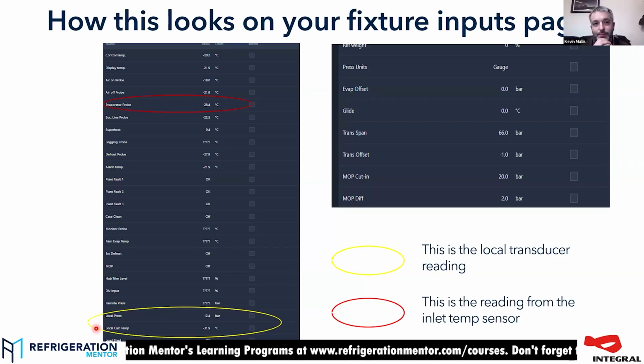100%. Especially when you've got the suction probe there, and especially if you're somewhere where, let's say you've got an electric defrost heater, when you fire that thing up out of defrost, that probe's going to have picked up a lot of radiated heat, and the valve is going to be all over the shop while that sorts itself out. Make sure you insulate it.